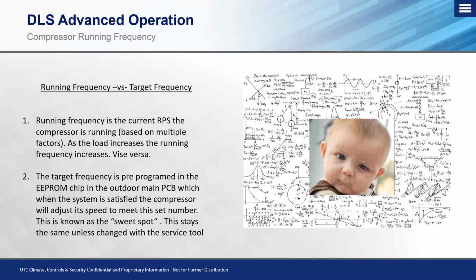This target frequency is pre-programmed from the factory, and in my experience, I haven't had a circumstance yet where this target frequency needed to be adjusted, but it is nice to know what that target frequency is and to confirm that the system actually is maintaining down to the target frequency. And this is something that we can have access to with the tool. Okay, so that's going to be the major differences, and also a good understanding of what running frequency is versus a target frequency on an inverter-based compressor.